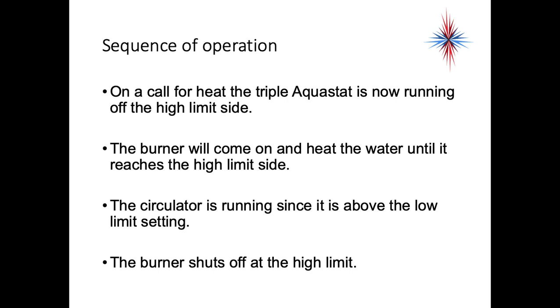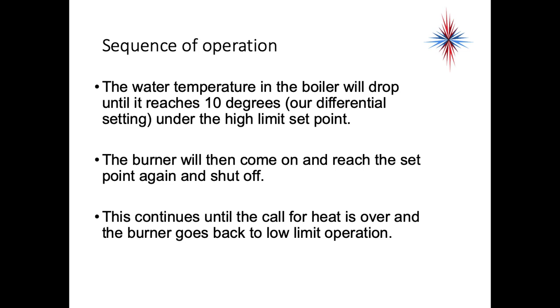On a call for heat, the triple aquastat switches over to run off the high limit side. The burner comes on and heats the water until it reaches the high limit setting — about 180 degrees. The circulator starts running as soon as the temperature gets above the low limit setting. The burner shuts off at the high limit, and the water temperature drops until it reaches 10 degrees below the high limit — about 170 degrees. The burner then comes on, reaches the setpoint again, and shuts off. This continues until the call for heat is over and the burner returns to low limit operation.